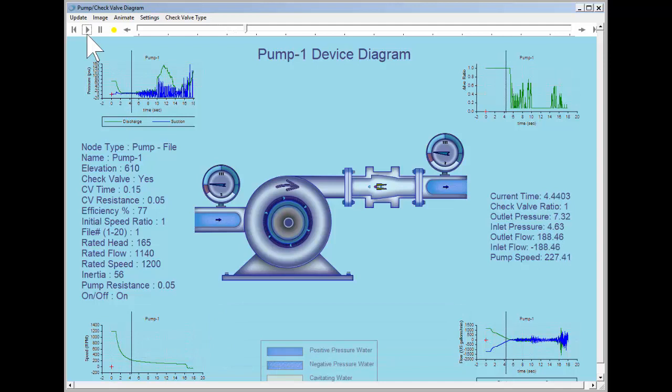At this time in the simulation, we can see the check valve closes, but doesn't stay closed. Instead, it oscillates in what is known as check valve chatter. Check valve chatter can cause both premature wear on the valve and possibly unacceptable swings in system pressures.